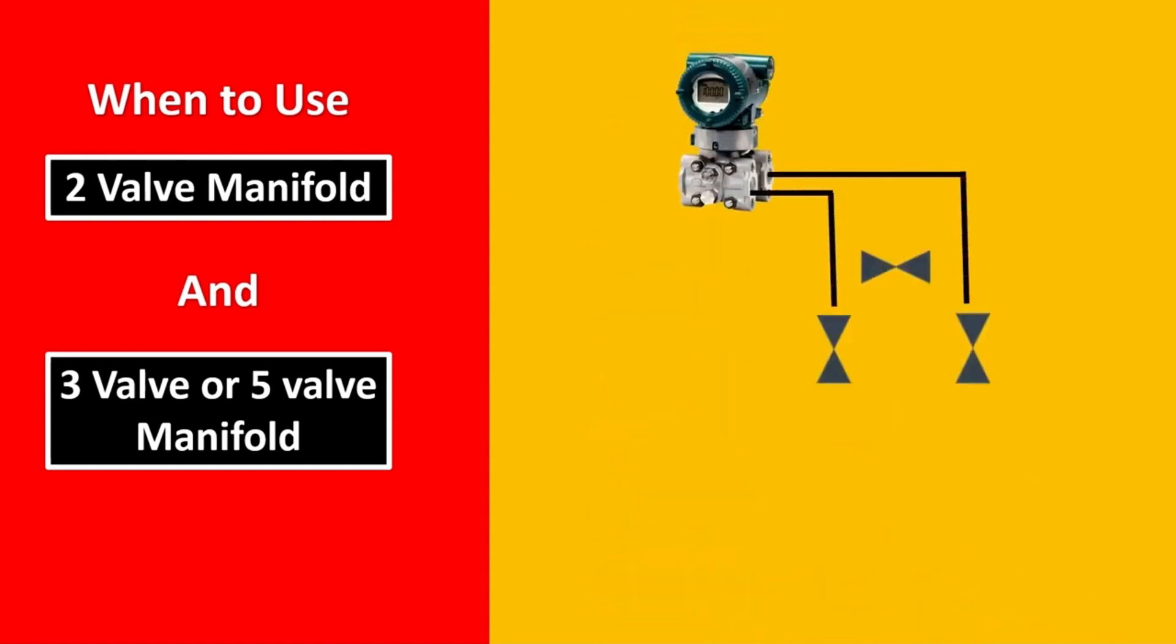Second is when you have 3 valve manifold. 3 valve manifold here is used for DP transmitters. You will have these 2 tappings or these 2 valves open and this one is closed.